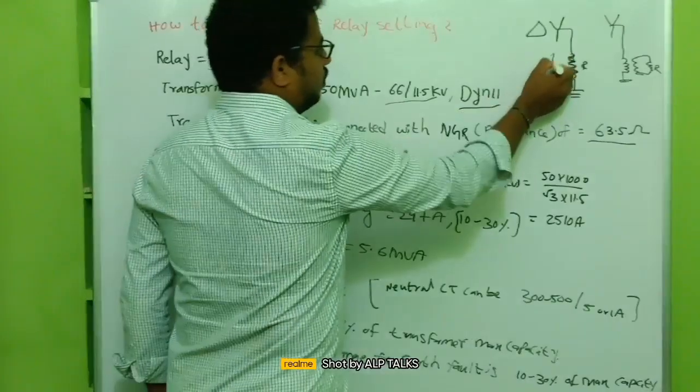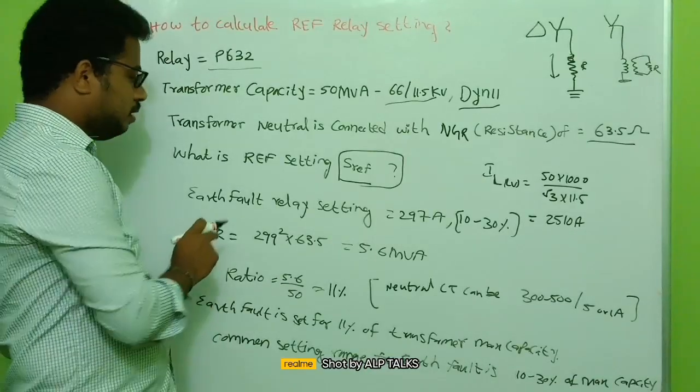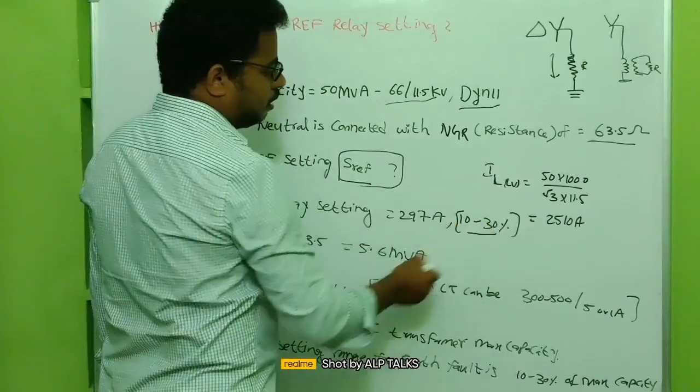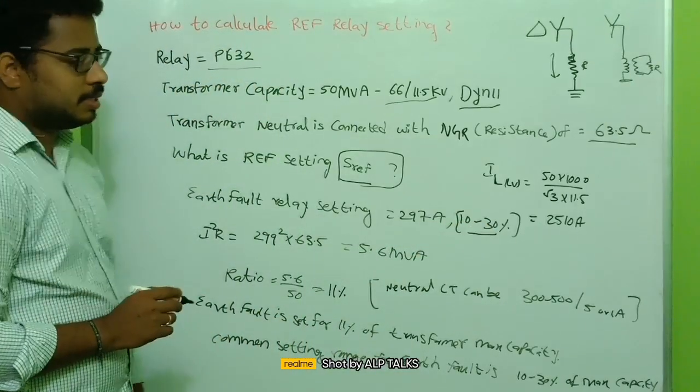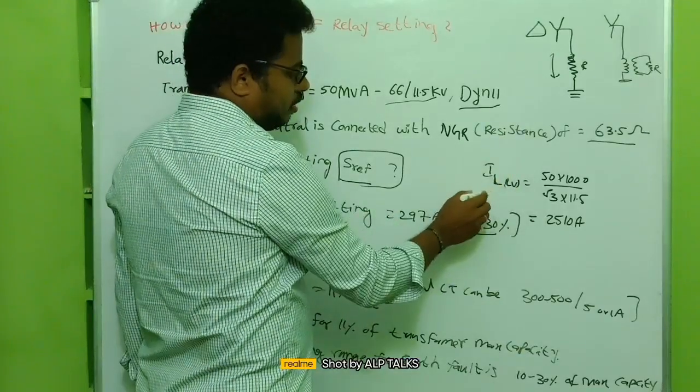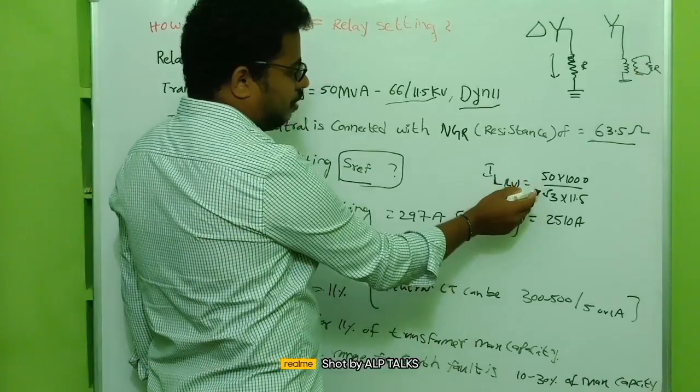Earth fault relay setting. So generally it will be 10 to 30 percent of the rated current of the transformer. For example, here on the LV side if we calculate the current, it is 50 MVA.